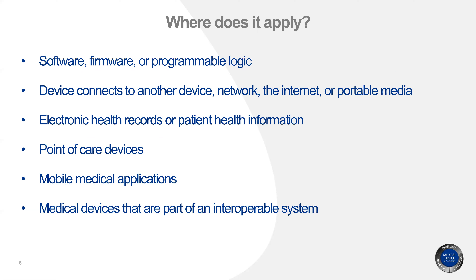Where does cybersecurity apply? Medical devices are connected — to another device (wireless or hardwired), to a network or the internet (Wi-Fi or BLE), or to portable media like USB or CD. Since the technological landscape for software and medical devices is rapidly growing, information is easily accessible by different means. In order to make a system secure, it is best to design it from the beginning. Do not consider cybersecurity as just a feature — make it a property of a well-designed system, just like how risk management goes hand-in-hand with the planning and design phase.